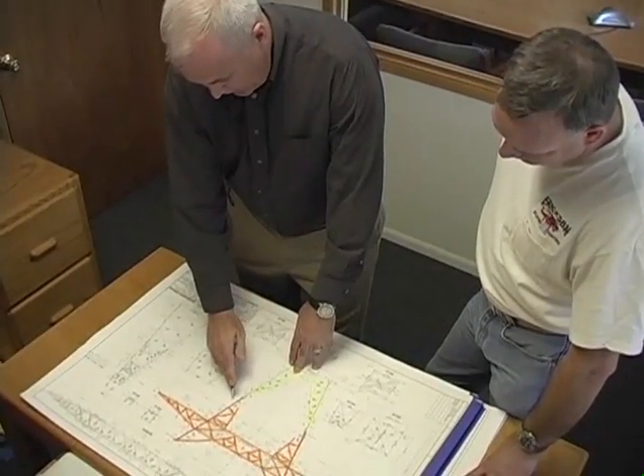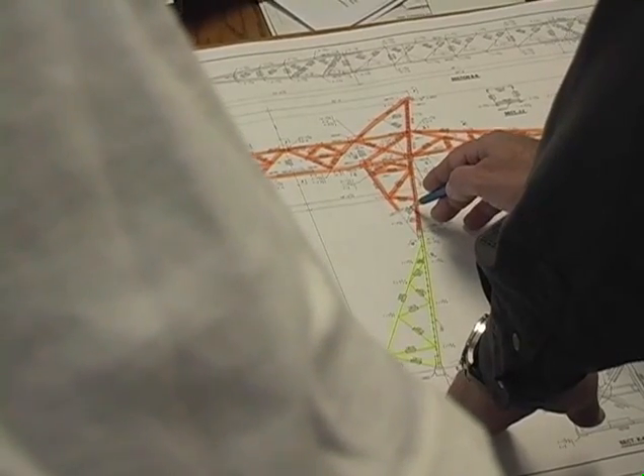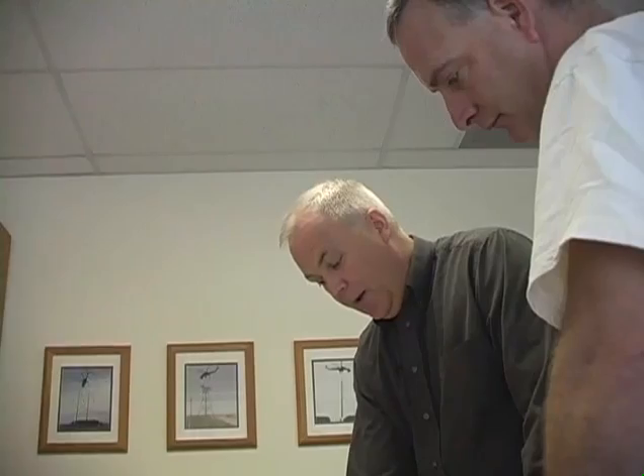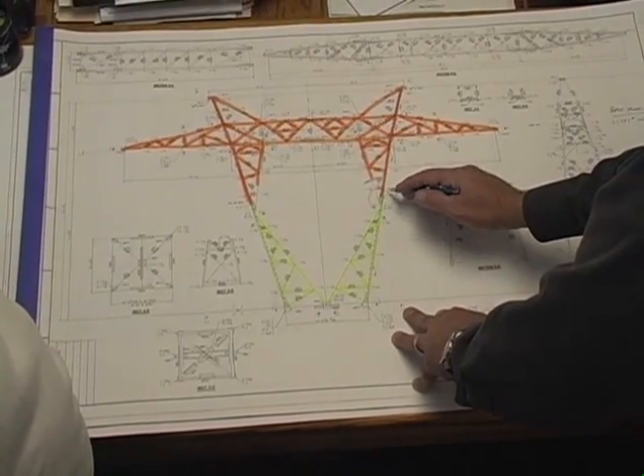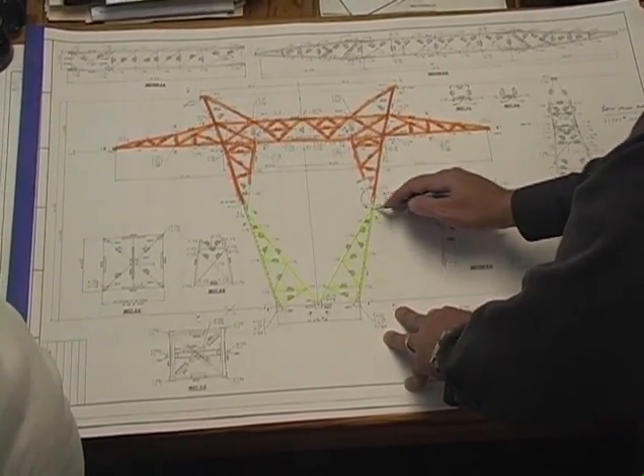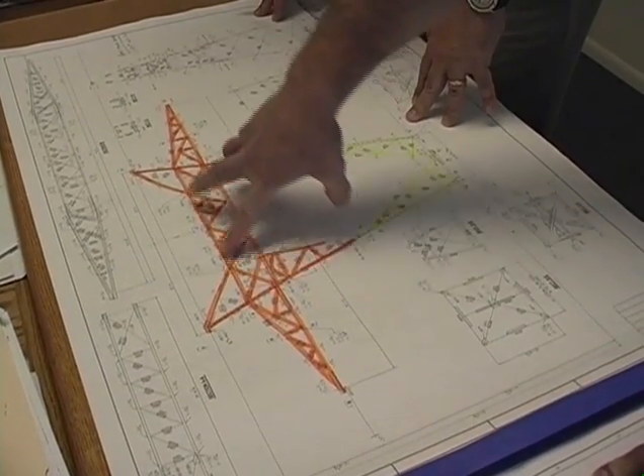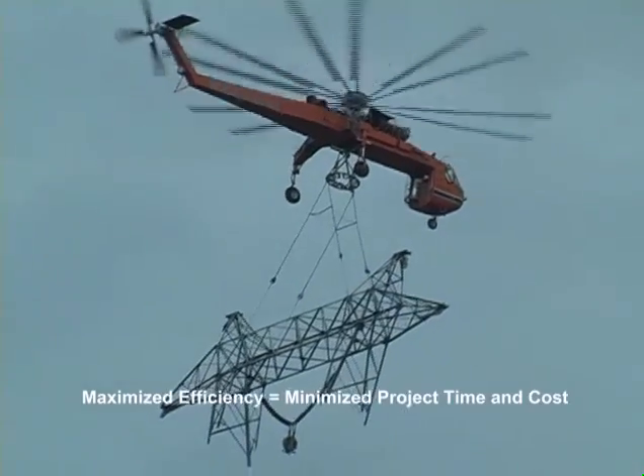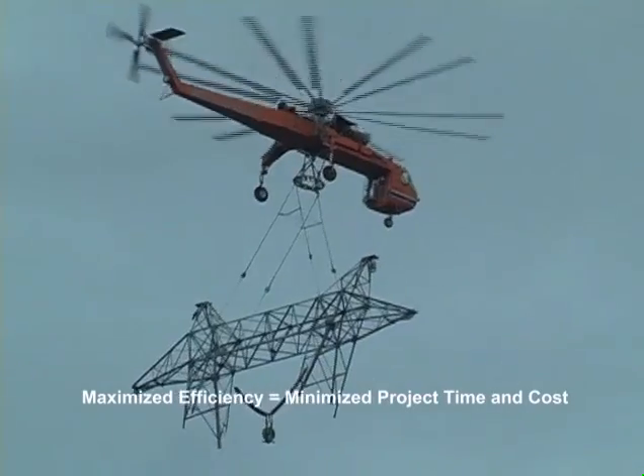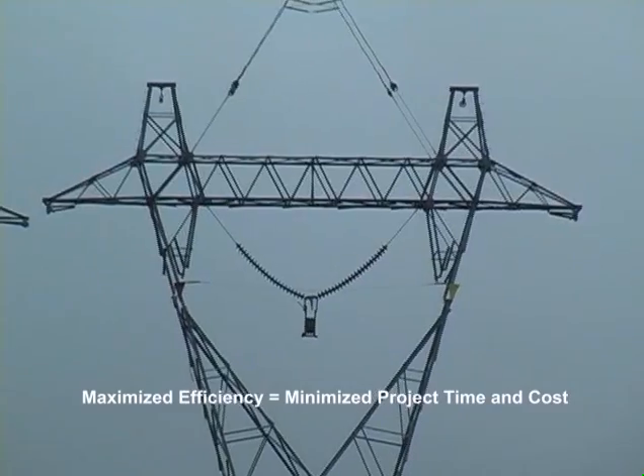These 500-kV single-circuit towers will require us to splice the haunch rail in approximately this location to eliminate any interference with the main rail as it sits on a custom-made stop incorporating a flower pot guide in this area. During the project planning phase, Erickson operations personnel can help you design the towers or sections to the lift capacity of the Aircrane. An optimal weight for the tower or section will maximize the efficiency of the helicopter and minimize flight time as well as your overall project time.